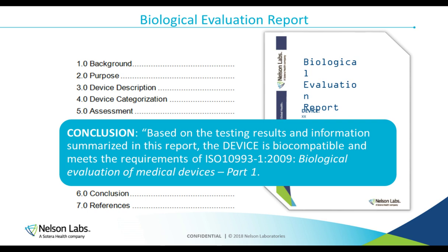Okay, so once you've gone through this process, so you've taken a look at the body of parts or devices that you need to have come into compliance with the MDRs. The first step was to make a biological evaluation plan. And in that plan, you take a look at the set of devices and say, okay, what biological endpoints have to be addressed? Once you know that, then the next step is to determine what your strategy is to go through and evaluate those, whether or not you have enough existing data to write a statement that supports it, or if you're going to have to do biological testing.